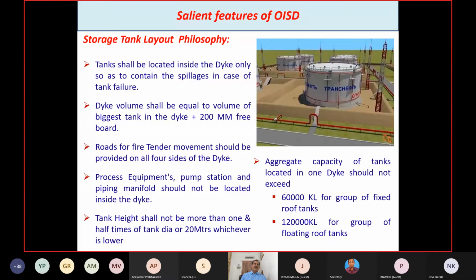The storage tank layout philosophy. Actually, the storage tanks shall be located inside the dike only, so as to contain the spillages in case of tank failure. And the dike volume shall be equal to the volume of the biggest tank in the dike, in addition to 200 mm of freeboard. And the roads for fire tender movement should be provided on all four sides of the dike. Here, the road's width is very important, and the road radii at the road junction should also be designed in such a way that movement of larger fire trucks is possible, that is more important.